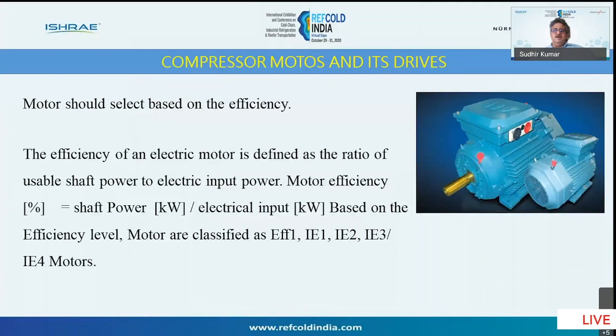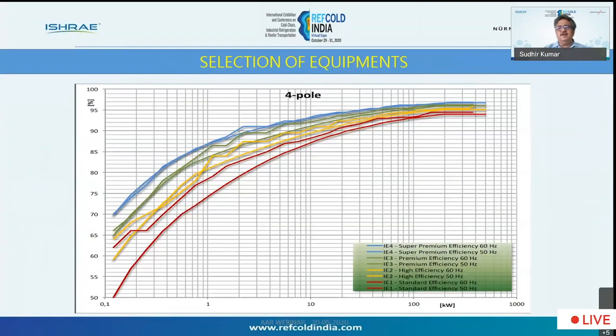Next comes the motor selection. Nowadays, a lot of motor efficiencies. We were seeing EFF1 and EFF2 in earlier days. Now the motor efficiencies are being classified as IE2, IE3, and even IE4. The latest generation motors are IE4, whereby you save power and the payback period is approximately 2 to 3 years if you use IE3 or IE4 motors. The difference between IE3 and IE4 is not much, but you will definitely find a power saving between IE1 and IE3 or IE4 motors.